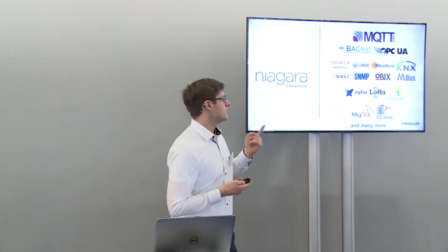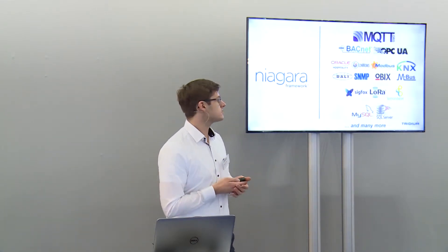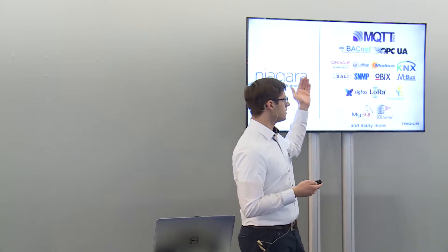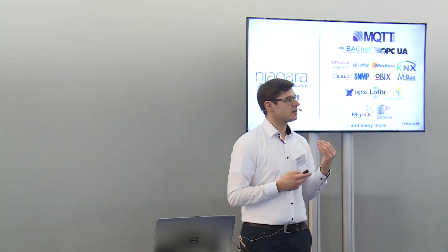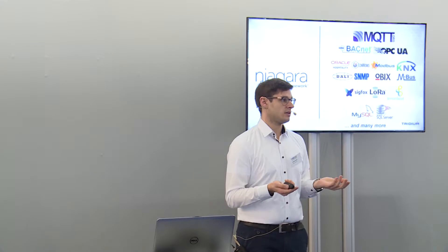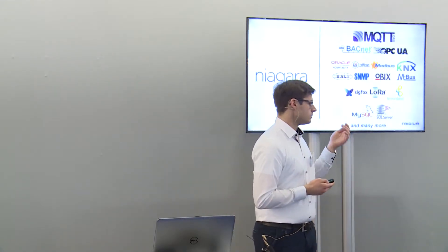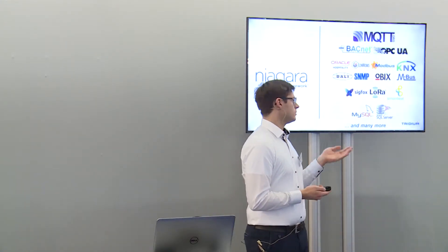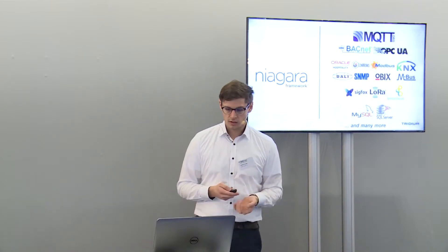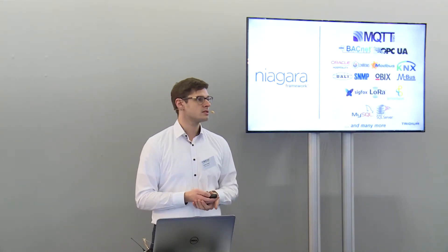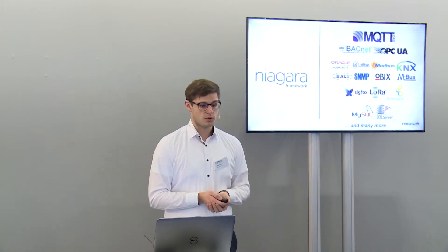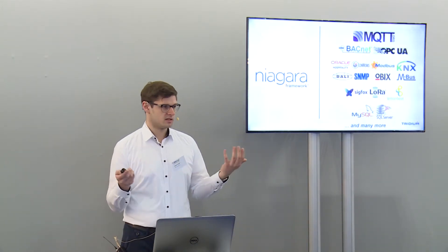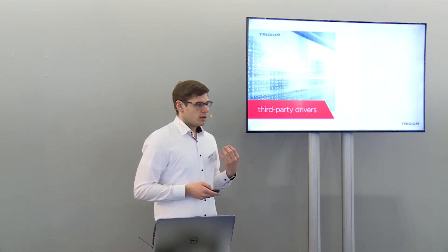We can integrate edge-level devices such as Sigfox, LoRa, and LonWorks devices, and of course the usual protocols like KNX and DALI. We can bring this data up to the cloud with MQTT or other RESTful web services, and you can connect Niagara to your company's ERP system via SQL or MySQL databases, or simply export data as a CSV file.